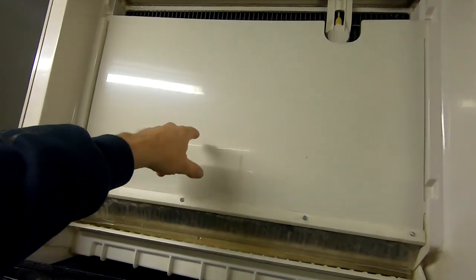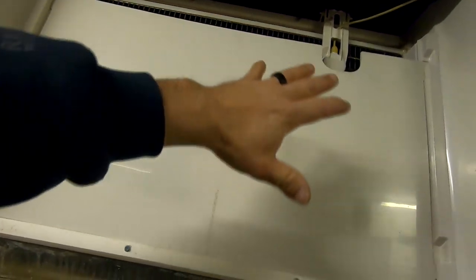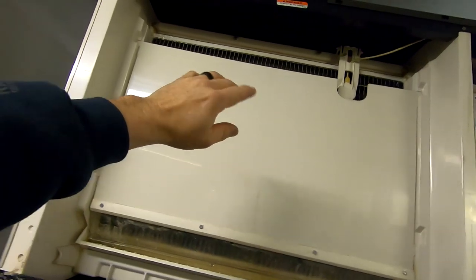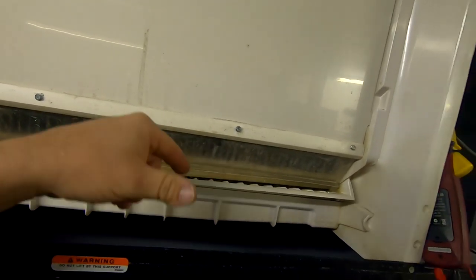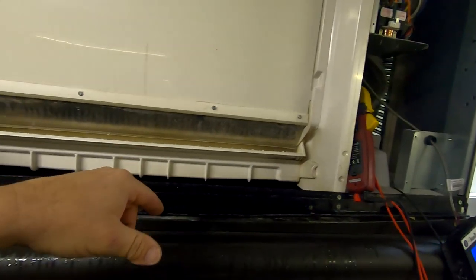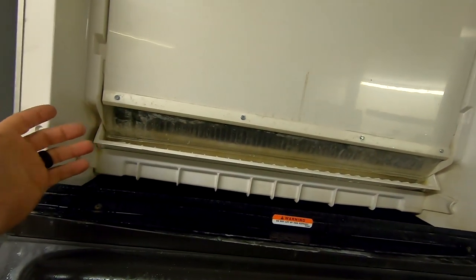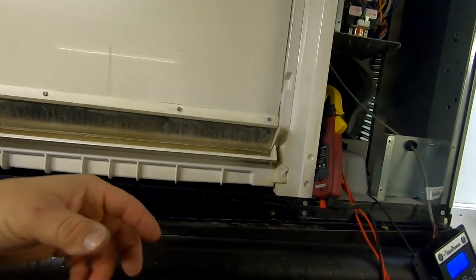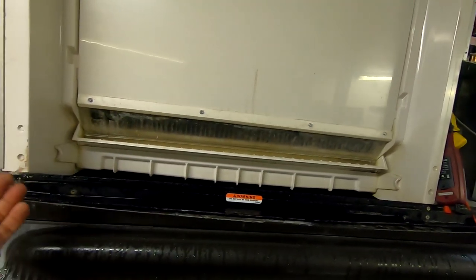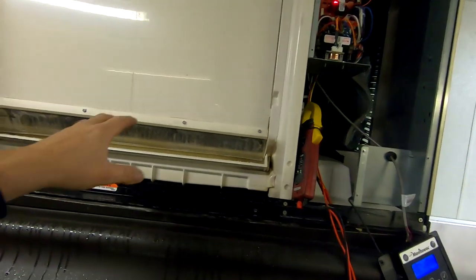Low on charge, large temperature drop. Correct charge, it'll be usually seven or less. But that's just the rule of thumb. Now by not having this curtain on here and this door off, the heat can cause this thing to slush. What can happen is the slush will build up down below here to trick out your water sensor.